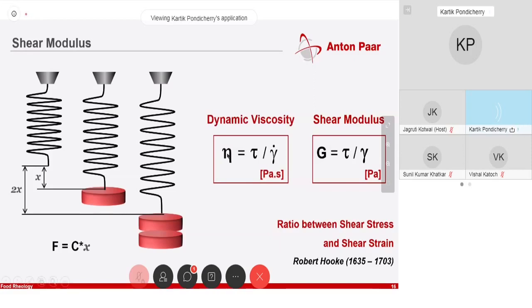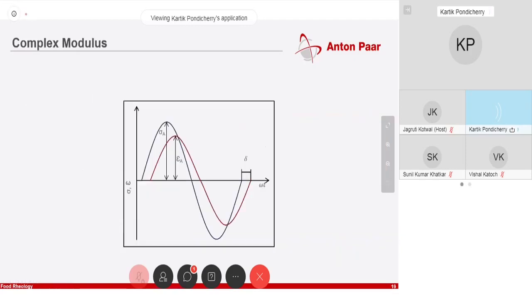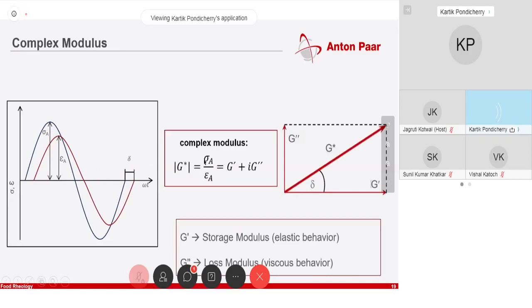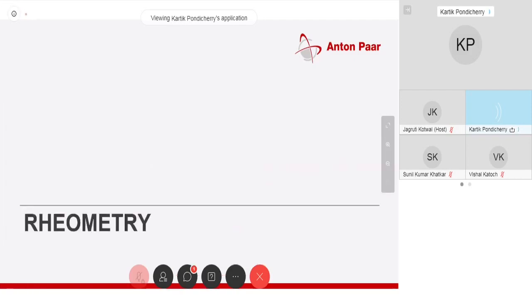If you compare viscosity with shear modulus, you might see a lot of similarity. But this involves shear rate versus shear strain. To understand that, we need oscillatory measurements. Without going too deep, you will see that you have the stress amplitude and the strain amplitude, and something called the phase shift delta, which is the lag or lead between the input and output. You take the stress amplitude over the strain amplitude — the absolute value is G*, which is the complex modulus. When you plot G* at angle delta, you get the storage modulus and the loss modulus as the x and y intercepts. We don't have to worry about the math because it's all done by the software, but it's important to understand how we get there.